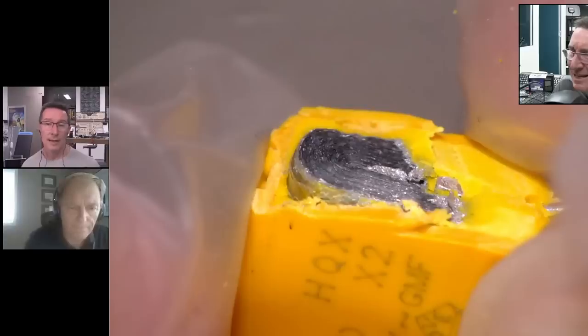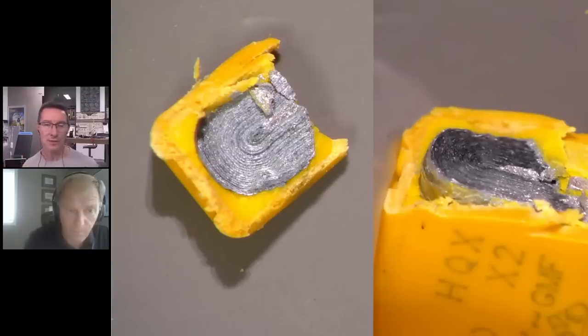So with the ones that we tore down here, where's the sealing point? Is it the potting? Is that what they're trying to do, seal it as best they can? Yes, it would possibly be at the perimeter of the metallization to the encapsulant. Right, okay. And then through the Schoopage on the side, really. It would come in through the side. It wouldn't come in through the actual film wrap, because I would imagine that's pretty sealed. That's correct. It would be at the interface of Schoopage or some errors or voids in Schoopage.